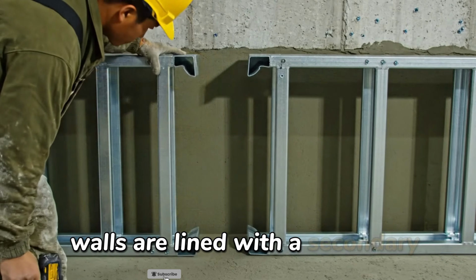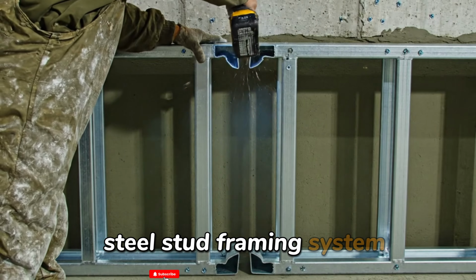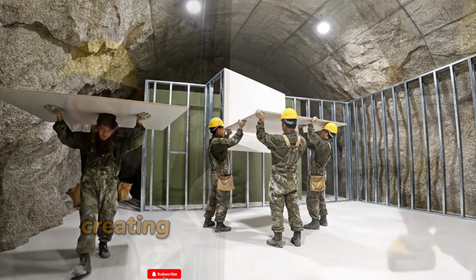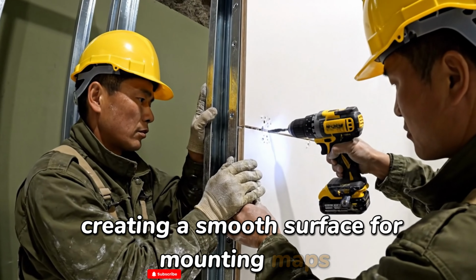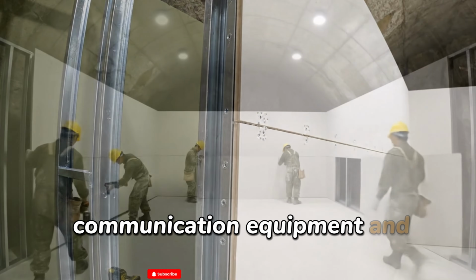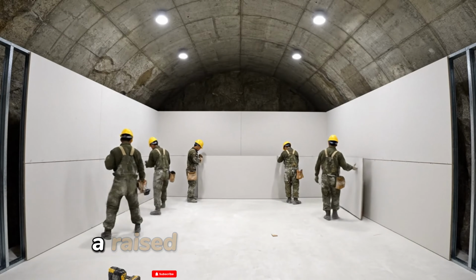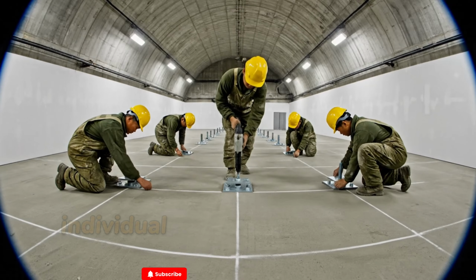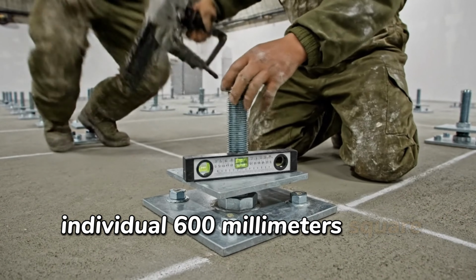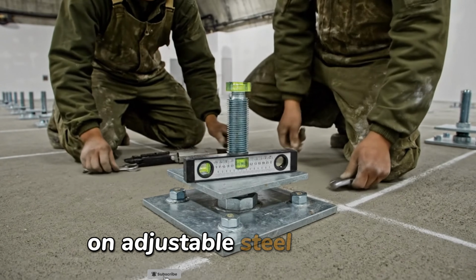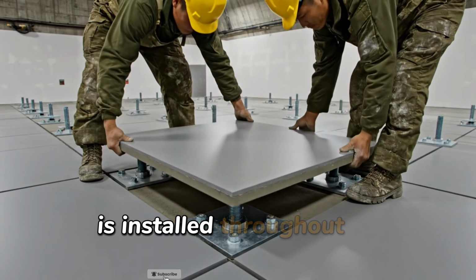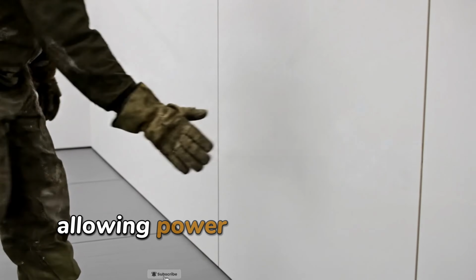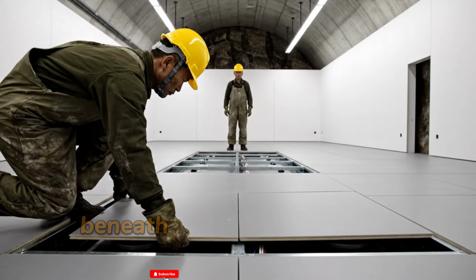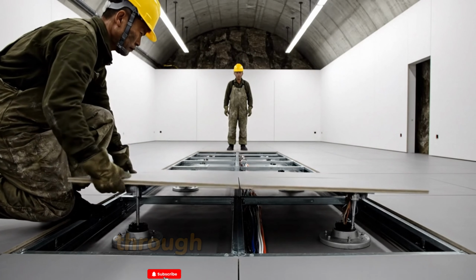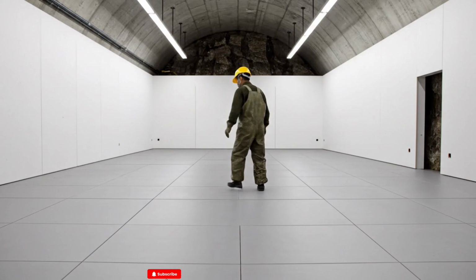Walls are lined with a secondary steel stud framing system covered in plasterboard, creating a smooth surface for mounting maps, communication equipment, and tactical displays. A raised access floor system, individual 600 mm square floor tiles on adjustable steel pedestals, is installed throughout the command room, allowing power and data cables to run freely beneath the floor and surface anywhere through removable tiles.